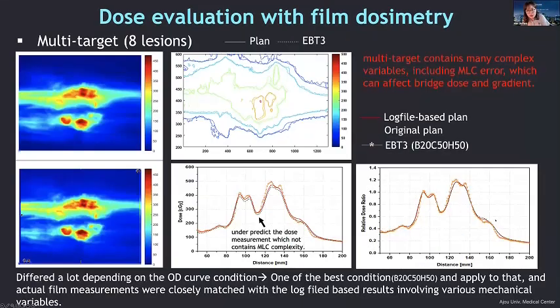The multi-target film measurement results are shown here. The multi-target case contains many complex variables, including MLC error, which can affect bridging doses and gradients a lot. So the results of this case differed a lot depending on the OD curves and conditions. But we selected one of the best conditions and applied that. The actual film measurements more closely matched the log-based result, which involves the various mechanical variables. The original plan significantly under-predicted the measured dose, as it does not contain MLC complexities.